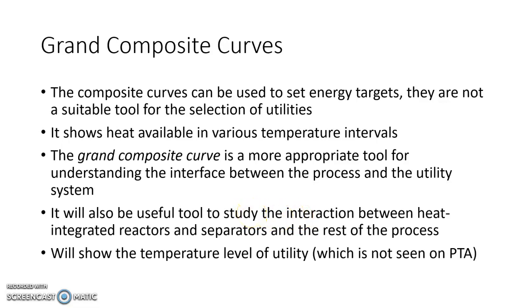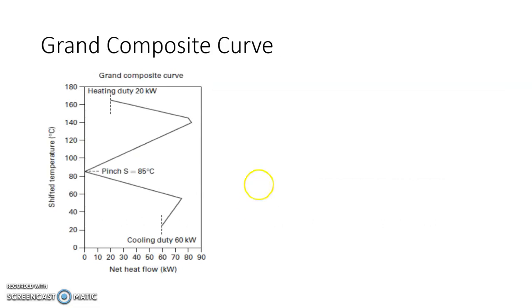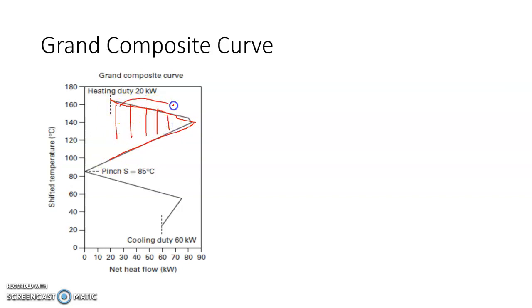The GCC will show the temperature level of the utility, which cannot be seen in Problem Table Analysis. In a typical Grand Composite Curve, this area shows the amount of heat that hot streams can provide, and the cold stream moves in this direction — there is an exchange between hot stream and cold stream. These are called energy recovery pockets, where cold streams receive energy and hot streams give up energy. The remaining portions represent your cooling duty and heating duty. The pinch point is visible on the curve.